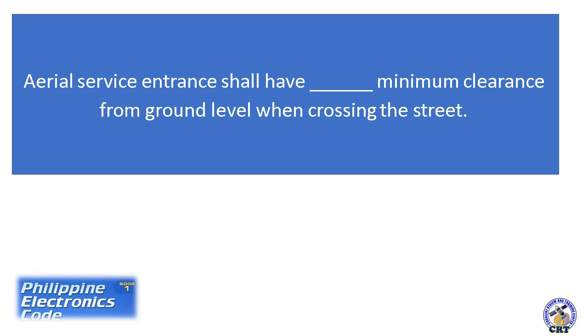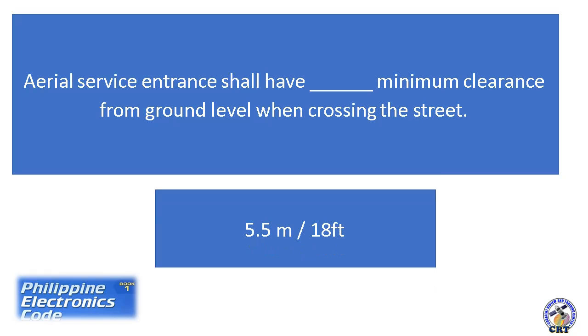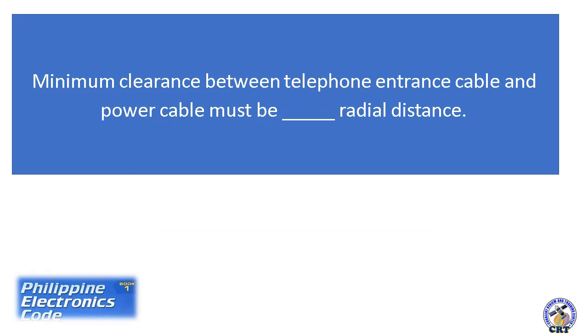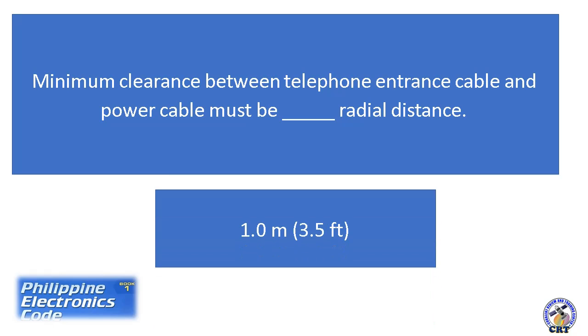Aerial service entrance shall have blank minimum clearance from ground level when crossing the street. It is 5.5 meters or 18 feet. Minimum clearance between telephone entrance cable and power cable must be blank radial distance. 1 meter or 3.5 feet.